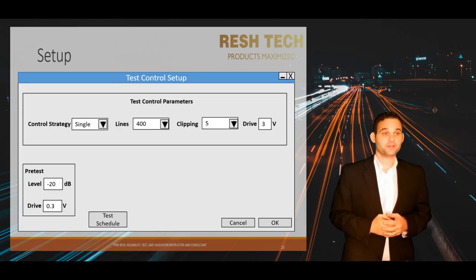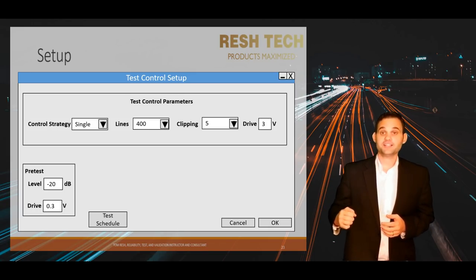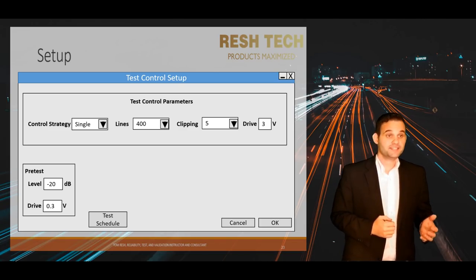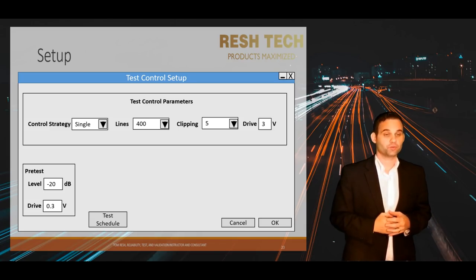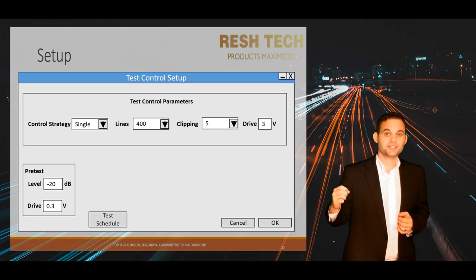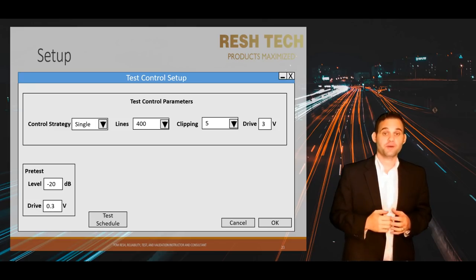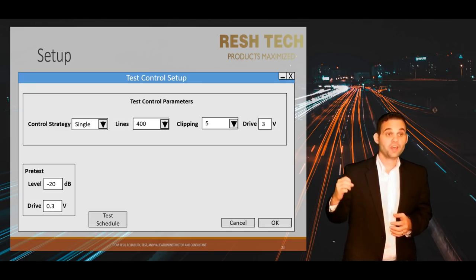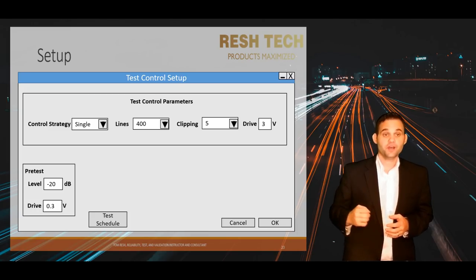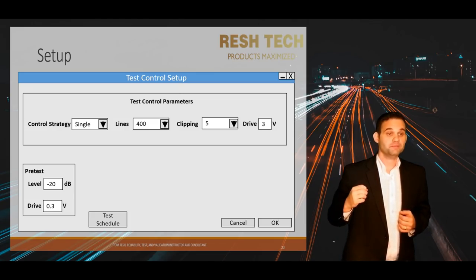On to the Test Control Setup Menu. The key fields you will see are control strategy, lines or control resolution, sigma clipping, drive voltage limit, pre-test settings, and test schedule. The control strategy options are typically single channel, weighted average, maximum, and minimum. Single channel is the option to select if you are only using one control accelerometer.